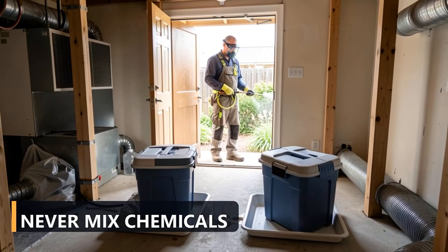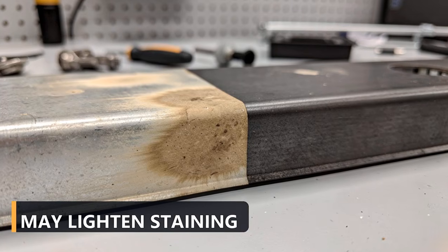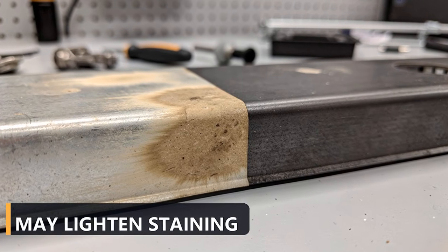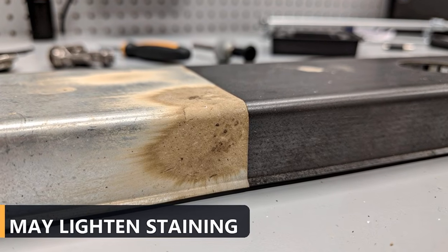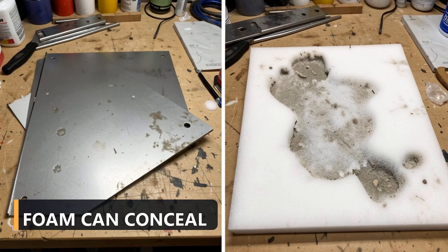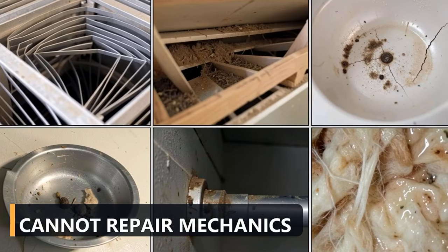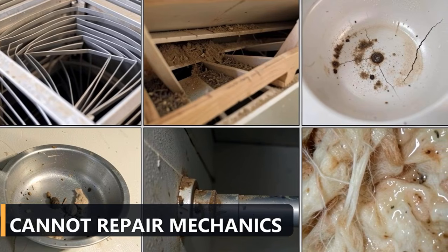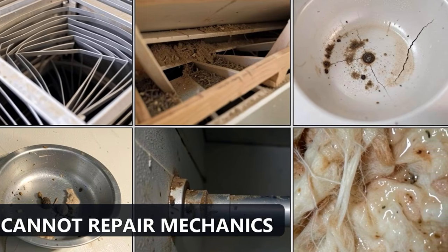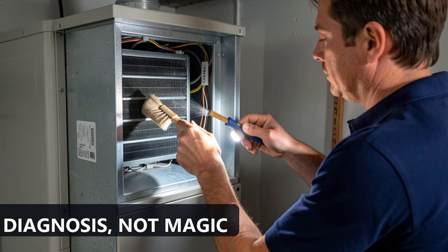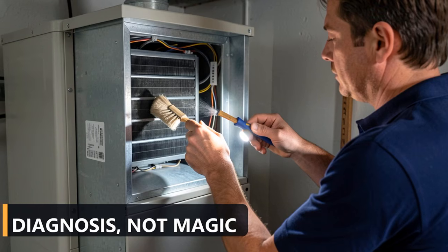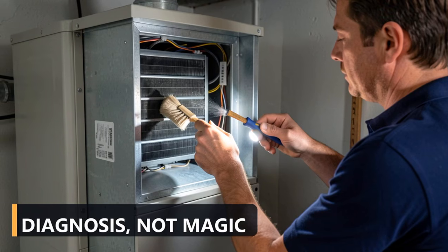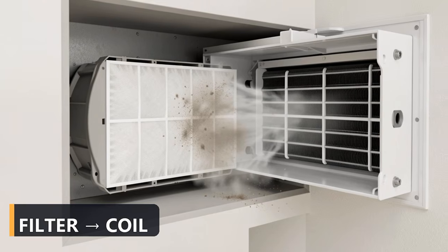So here is the honest verdict. Hydrogen peroxide may lighten exposed organic staining and loosen limited residue on a compatible, removable surface. It may also create spectacular foam that makes an incomplete job look finished. It cannot straighten fins, restore airflow, repair a pan, pull a solid clog from a drain, dry wet insulation, protect electrical controls, or eliminate the condition that caused growth.